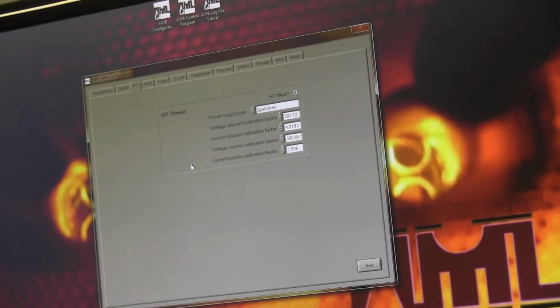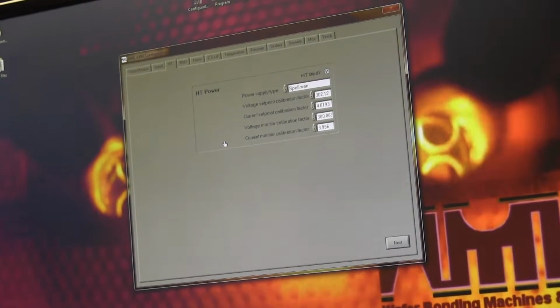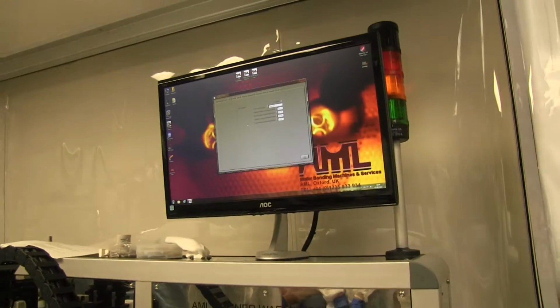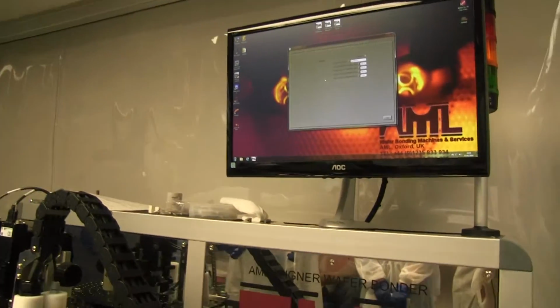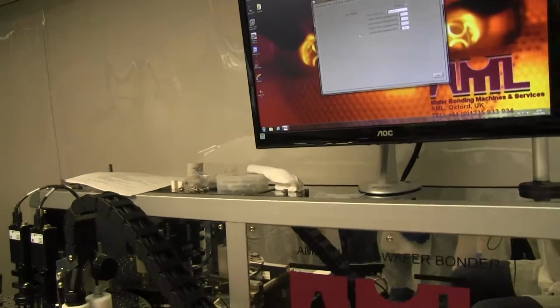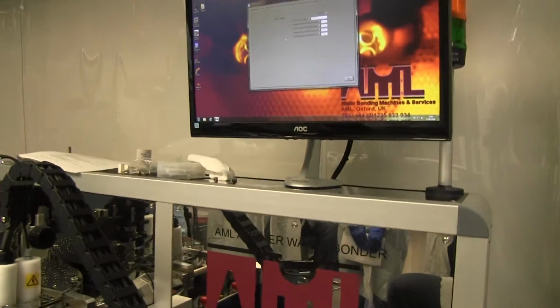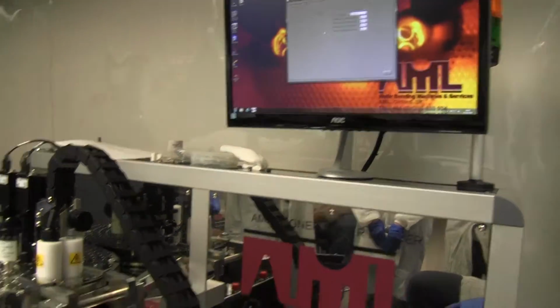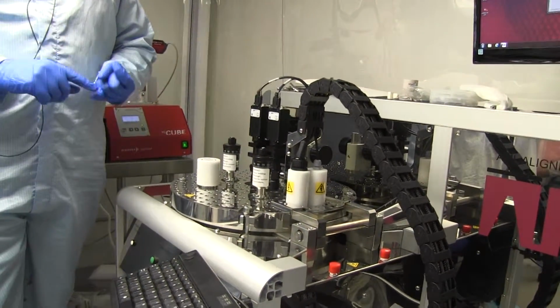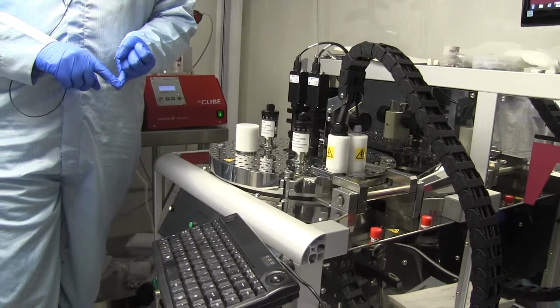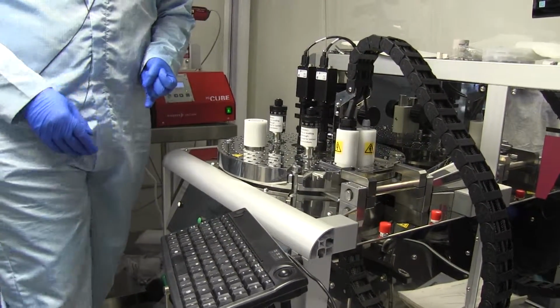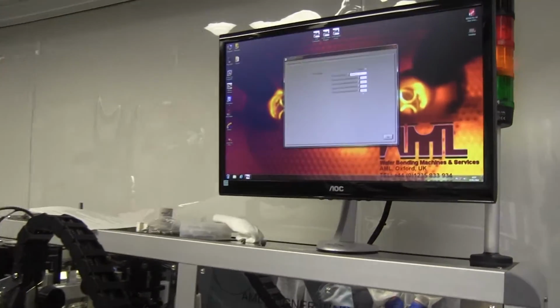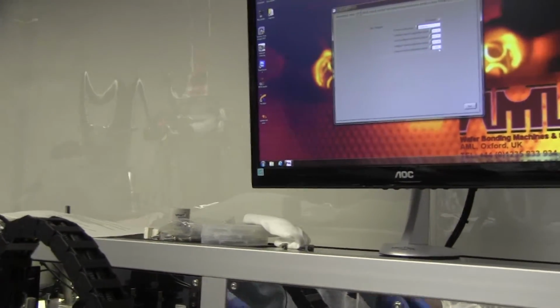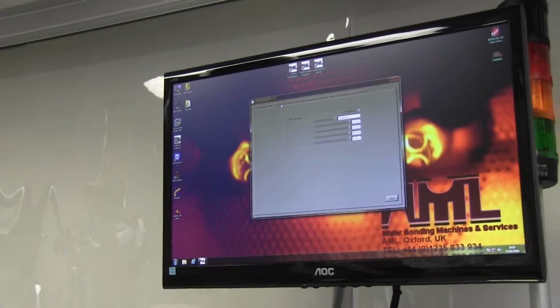Then there are some calibration factors. This is to calibrate any mismatch between the power supply and the PLC controller. Essentially, with those calibrations in place, we've used a calibrated meter to measure the voltage on the input side of the lid, and it's calibrated such that when you ask for, say, 500 volts, you get 500 volts. You don't get 505 volts or something like this. So any mismatch is taken up using these parameters. We've calculated those parameters in the factory, so you don't need to change them.